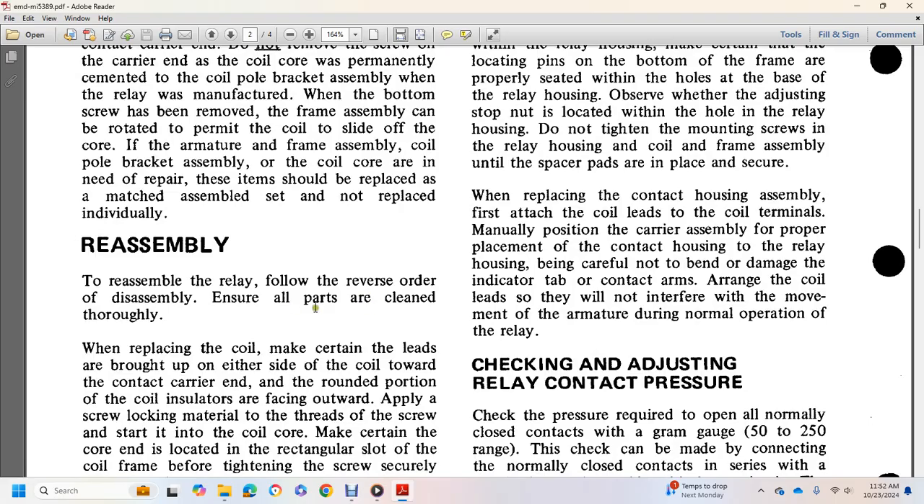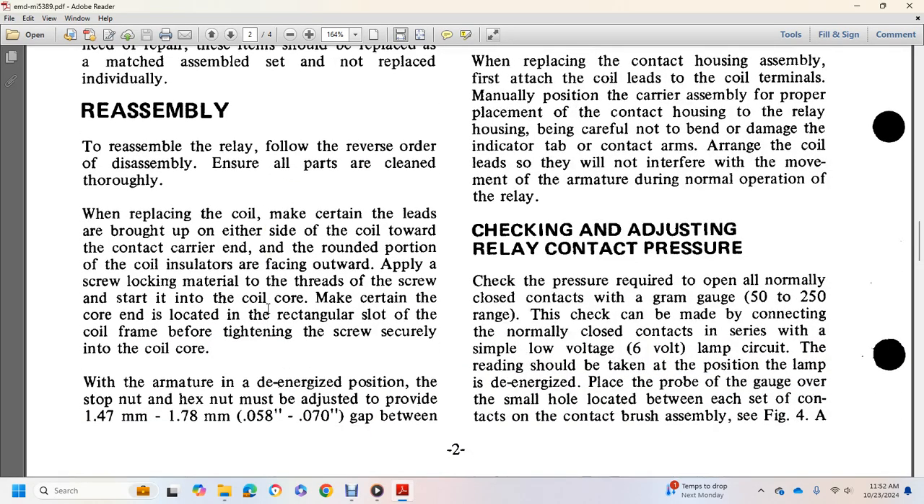Reverse the disassembly procedure to reassemble, ensuring all parts are cleaned thoroughly. Replace the coil, making certain the leads are brought up at either side of the coil. Place the contact carrier with the rounded portion of the coil, insulator facing outward. Apply screw-locking material to the thread and screw into the coil core. Make certain the core end is located in the rectangular slot of the coil frame before tightening the screws.